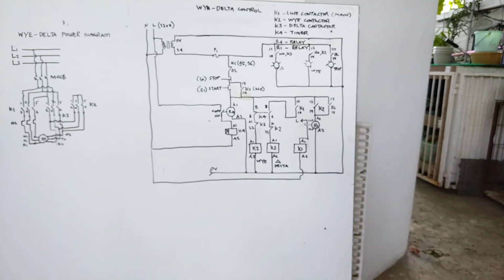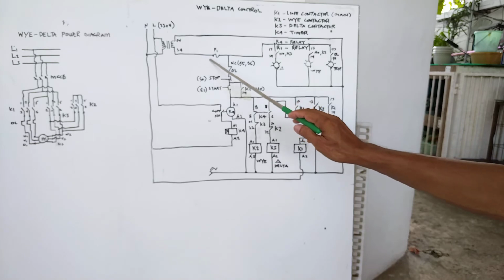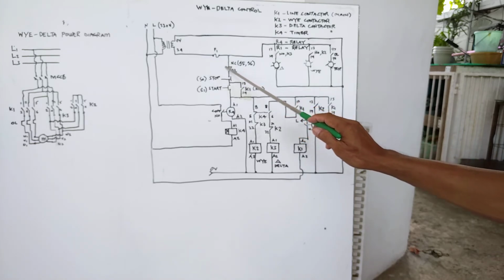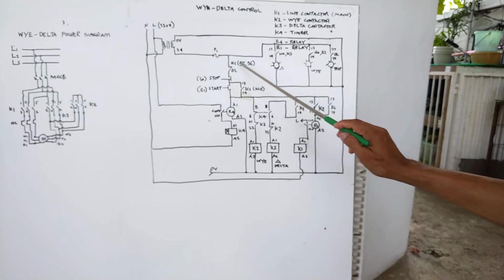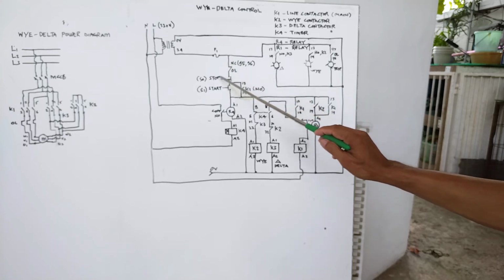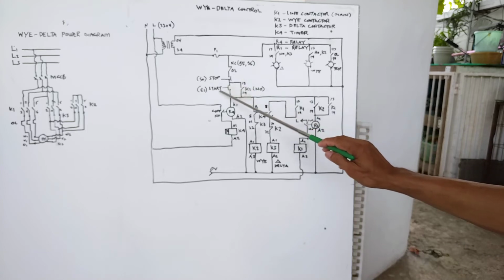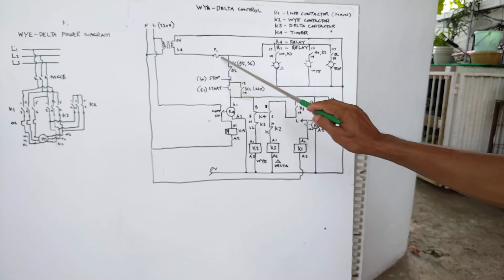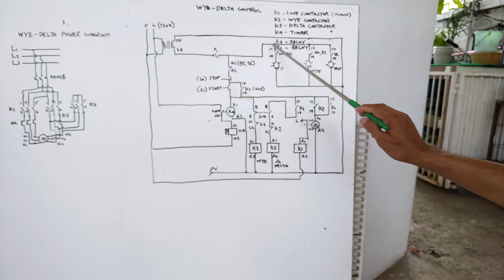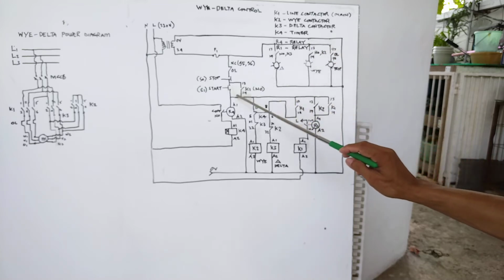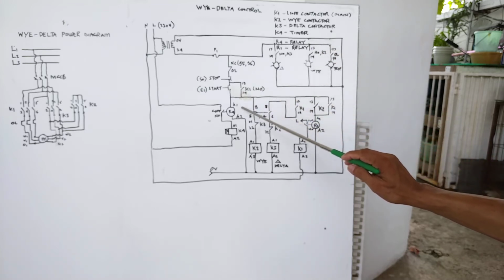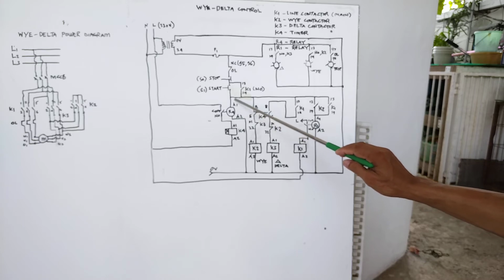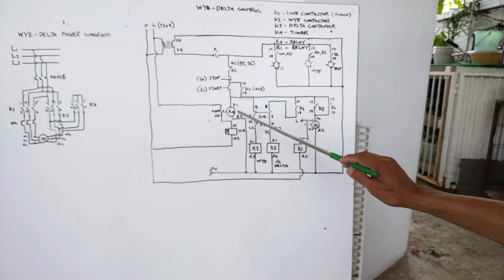Now, let's trace. My 24 volts will come here, go to the fuse, then to the normally closed contact of my overload. I'm showing the terminal here. Then I have my stop push button, which is normally closed, then my start push button, which is normally open. The first time we push this push button, the 24 volts flow like this, then 24 volts will also be available here. Then this relay coil will be energized because 24 volts will be present here and this one is connected to 0 volt.